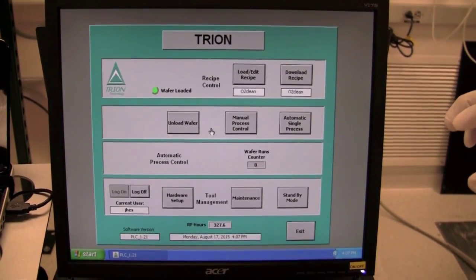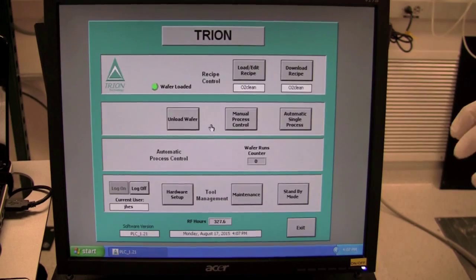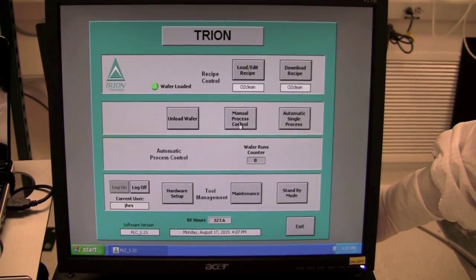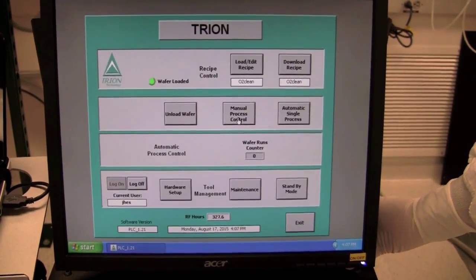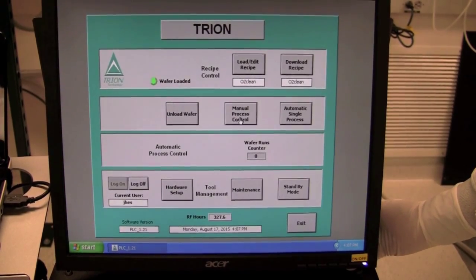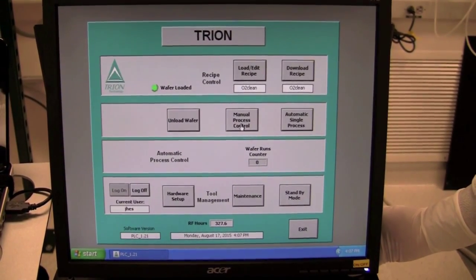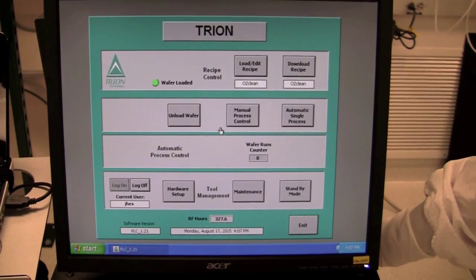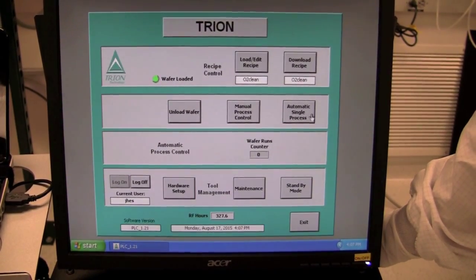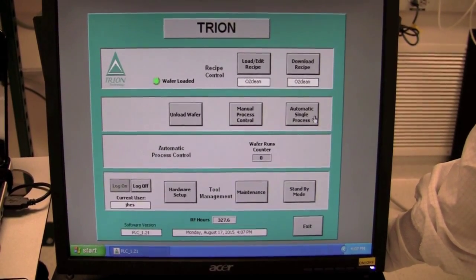Now that we're in the recipes and everything's loaded, we can begin running our process. Before we begin though, I want to make a distinction between manual process control and automatic process control. In manual, which is more for experienced users who have had the training, you can change a lot of other parameters, including the gas flows on the fly. But, for now, we're going to use the automatic single process, which is going to be the most commonly used for the average user.